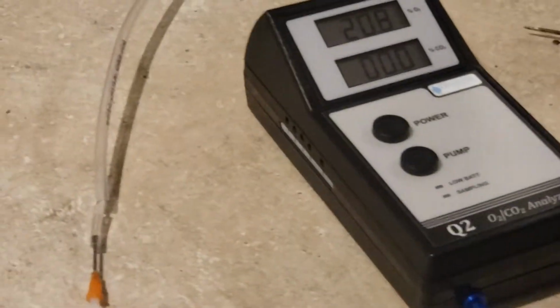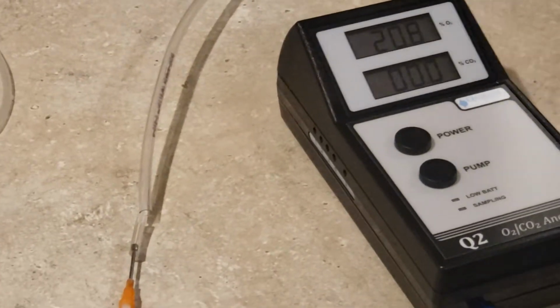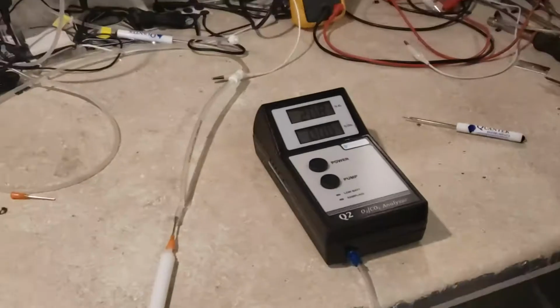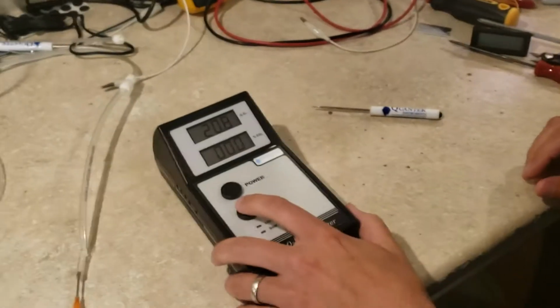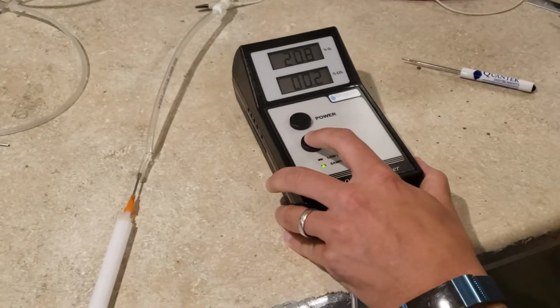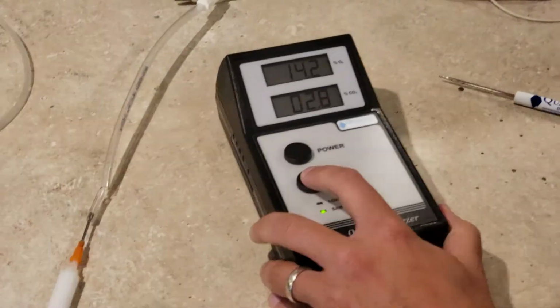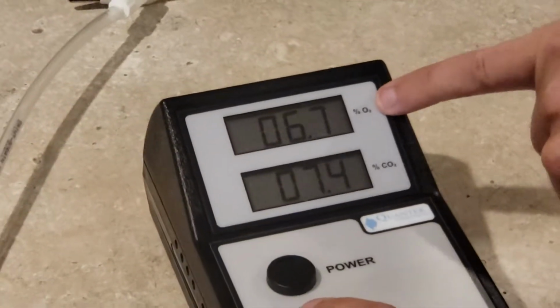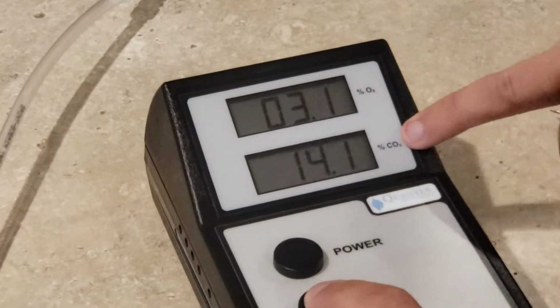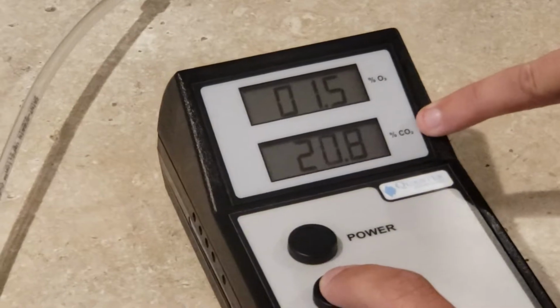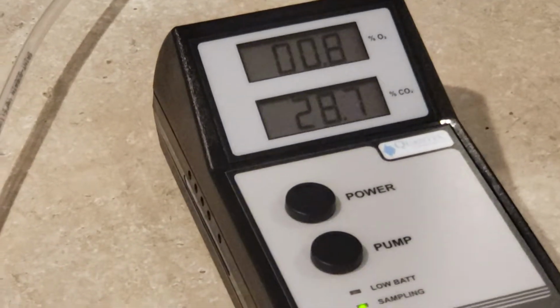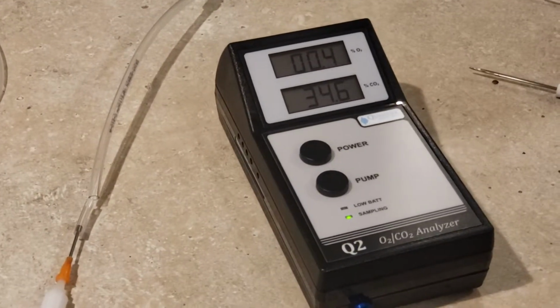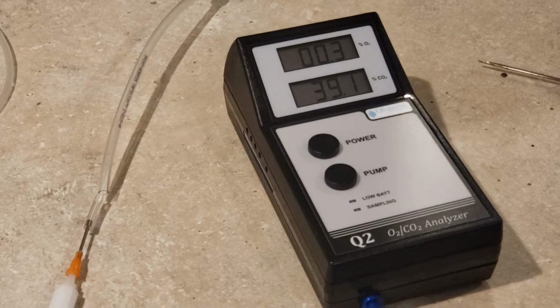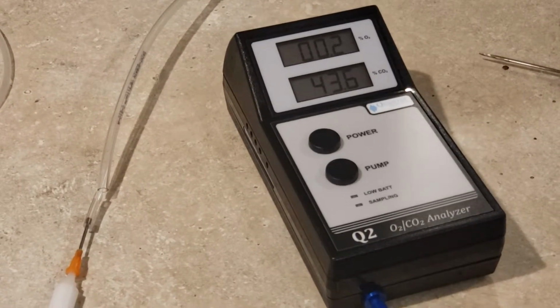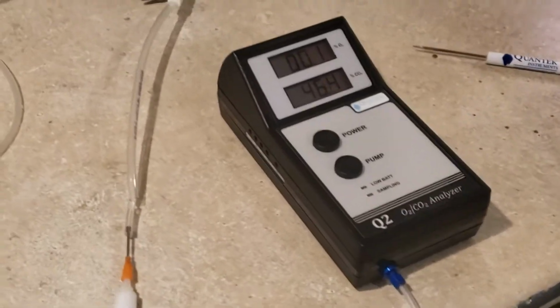So I'm going to calibrate with something that's in the middle of the range. The first thing that I'm going to do is find a 50% standard, and I'm going to get that flowing out of the tank, and then with the 50% CO2, we're going to go ahead and hit the pump button. And we're going to watch the reading start to change. Now you notice that the oxygen is going down, which makes sense because this is a 50% CO2 standard in nitrogen, and the CO2 reading is going up, hopefully towards 50%. It doesn't hurt to pump it a second time because you're just making sure that the air gets drawn through. So now we'll let it stabilize. While that's reaching its final reading, we're just going to turn the cylinder off.